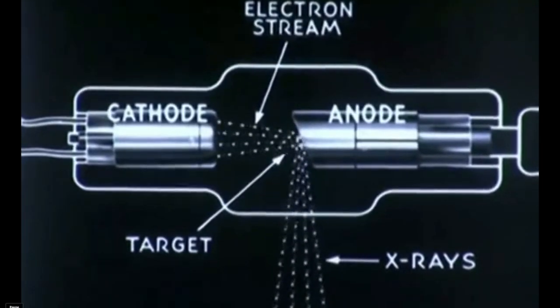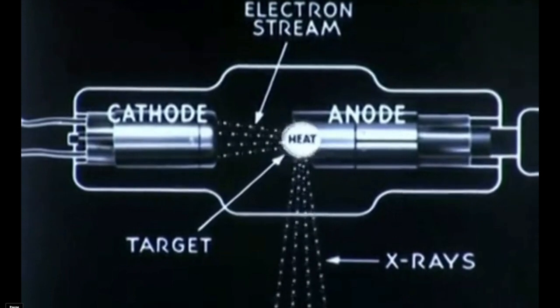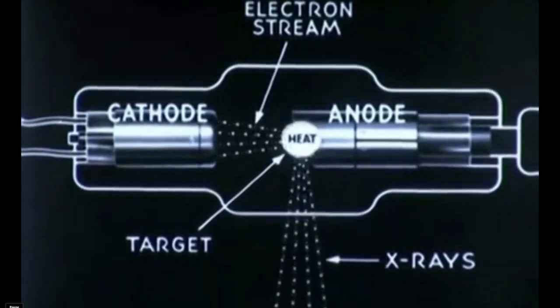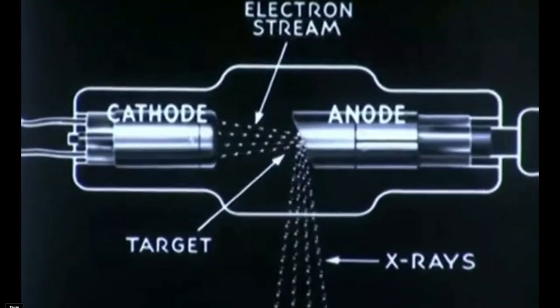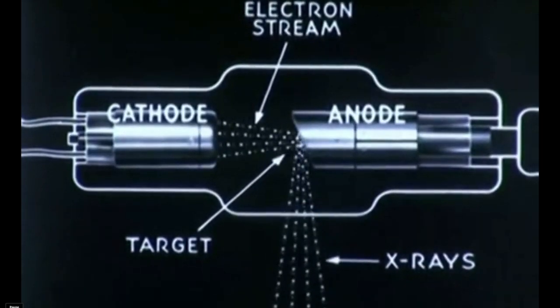Electrons are produced in the X-ray tube at the cathode filament by a process called thermionic emission, which is the release of electrons in response to heat. A current running through the filament causes it to be extremely hot, and electrons dissociate from the metal and form an electron cloud around the filament.